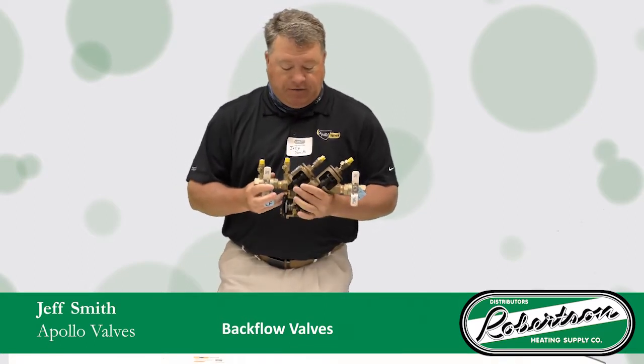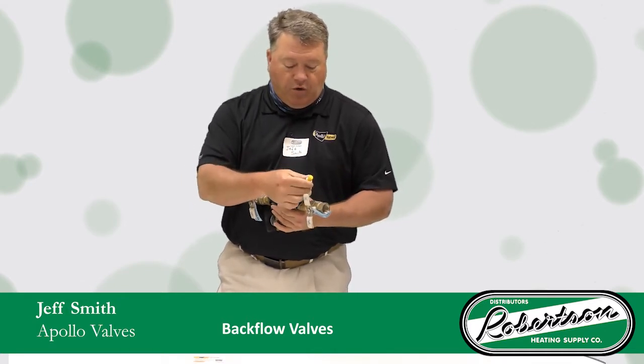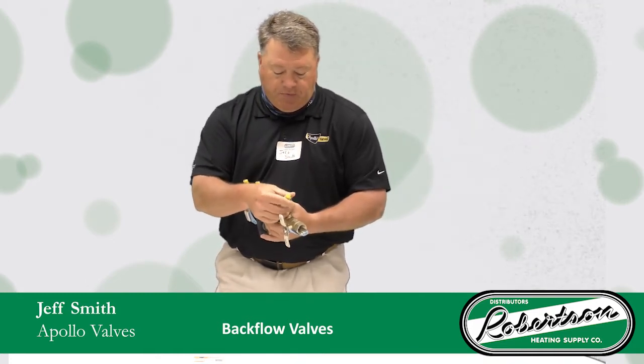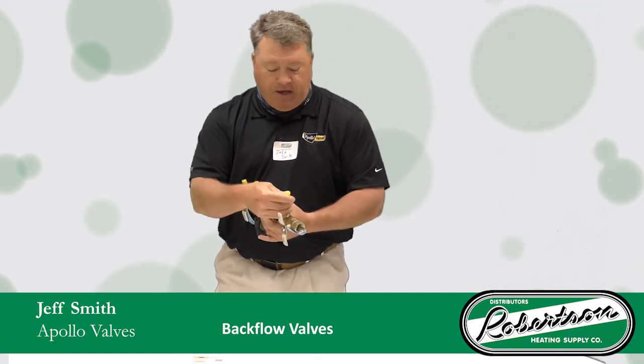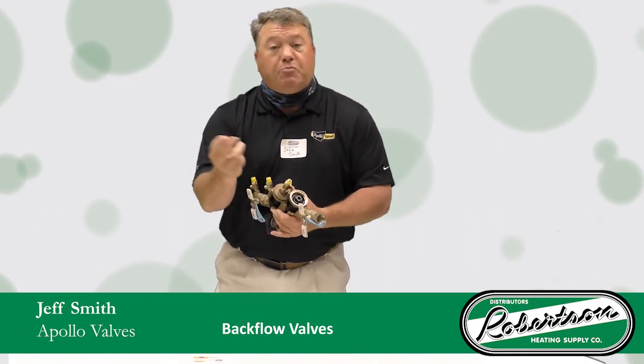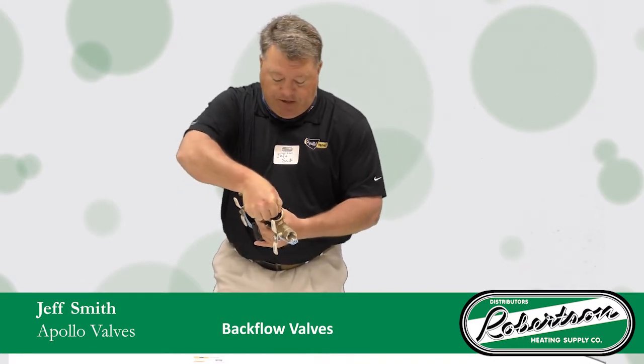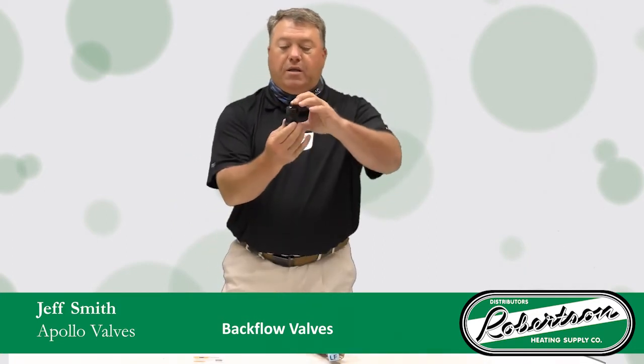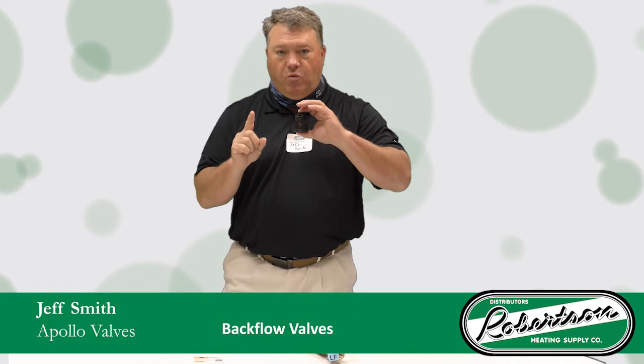Some of the items that we pride ourselves in is what we call the captured check. If you open up this port here, our competitors' spring is typically captured only by this particular cap. So when you take that off, springs tend to fly. With ours, we have what we call the captured check on the inside, so when you spin that off and wiggle it just a little bit, it will come out with the captured body with the spring. On the double check, the same repair kit is needed for both checks, so you only have to carry one type of repair kit.